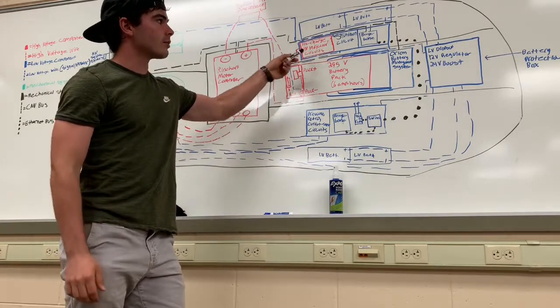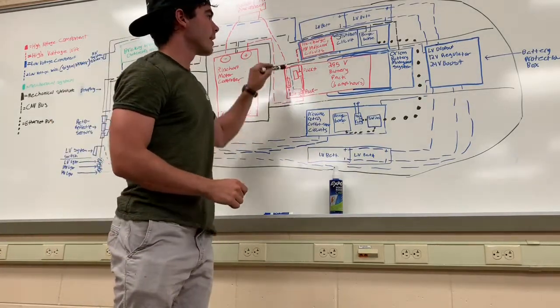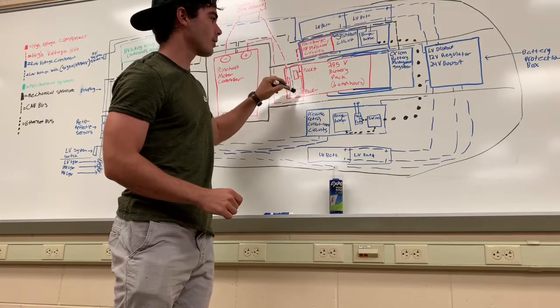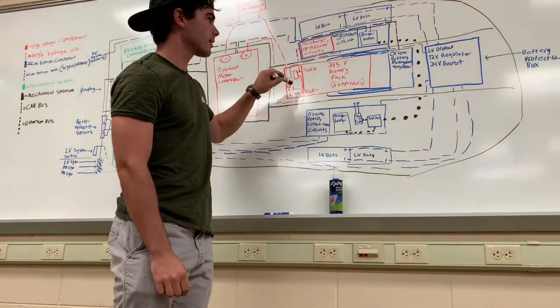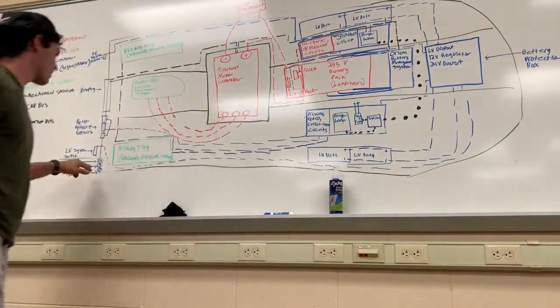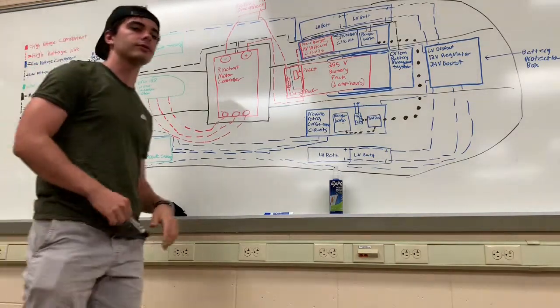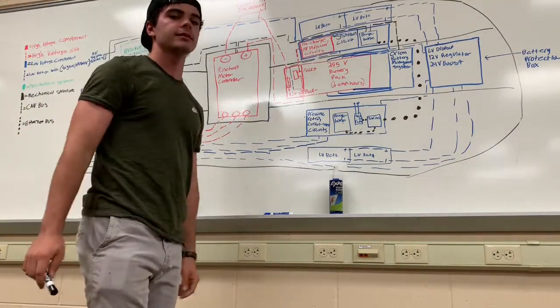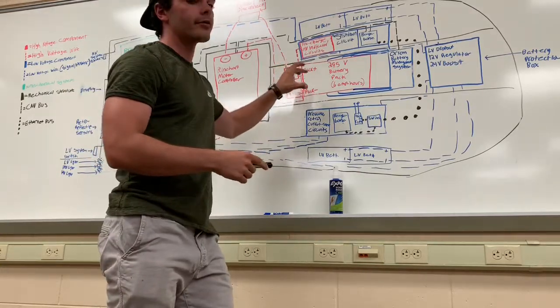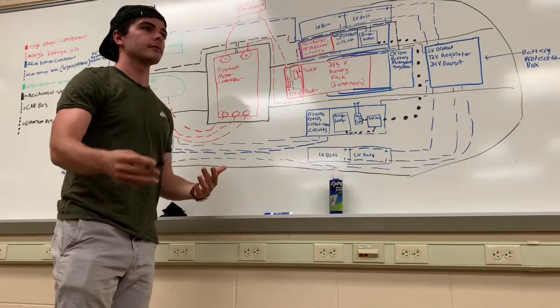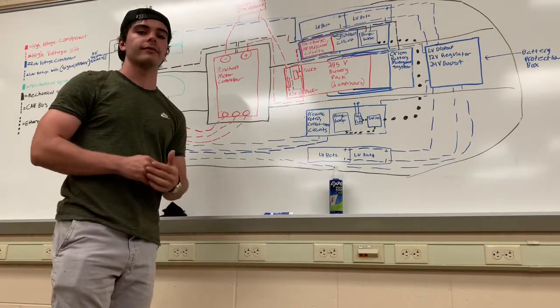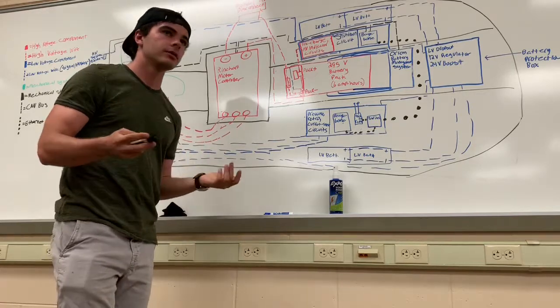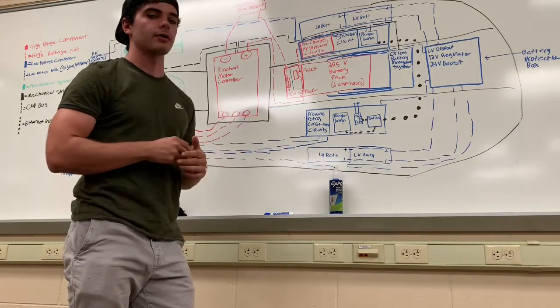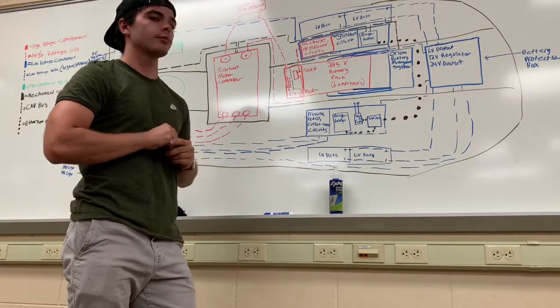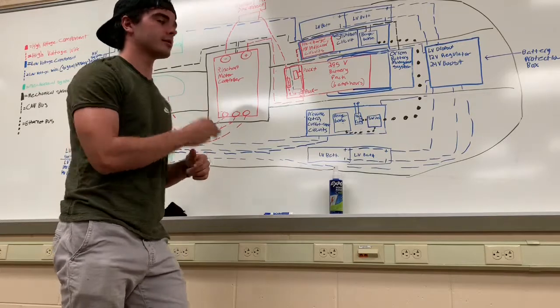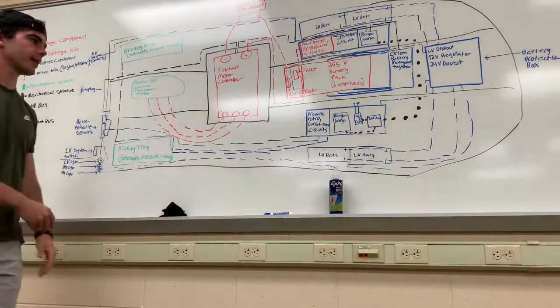The high voltage indicator circuit is wired directly to pack high and pack low on the battery pack. When the contactors are closed, it lights an indicator back here showing a complete high voltage circuit is present on the pod, mainly for safety. It's directly wired to the battery pack, not controlled via software, so if you lost low voltage power you'd still see the light. It's powered directly off the battery pack through a beefy step-down converter that steps it down to 12 volts to power this LED.